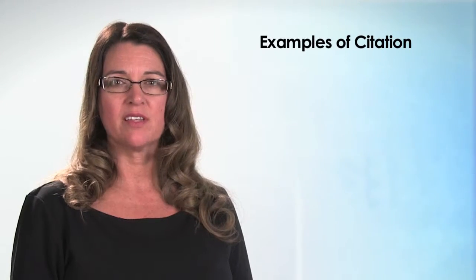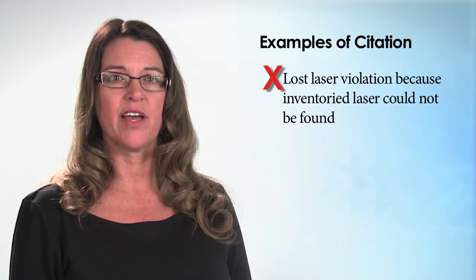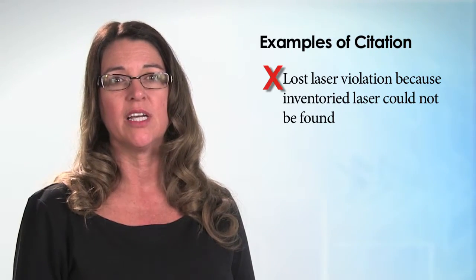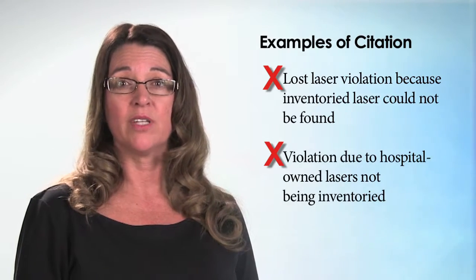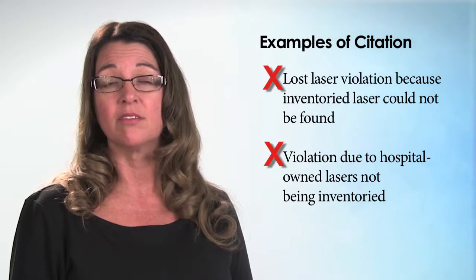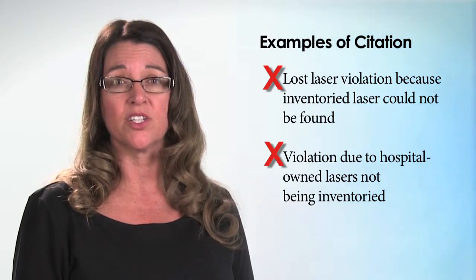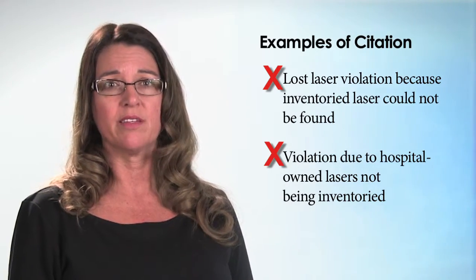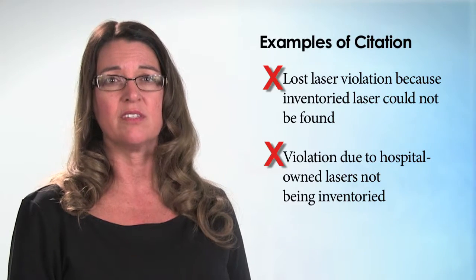In past surveys, some hospitals have been cited for lost laser violations because they were not able to locate lasers listed on their inventory. In other instances, hospital-owned lasers were not included in their inventory at all. It is advisable that your organization conducts a mock Environment of Care session. Richard will elaborate more on this, but first let's summarize the key points of these standards.